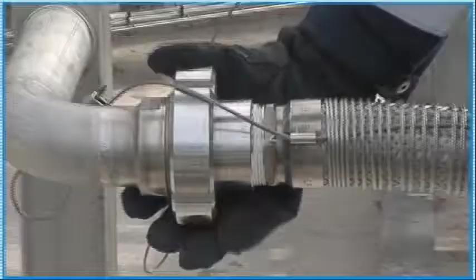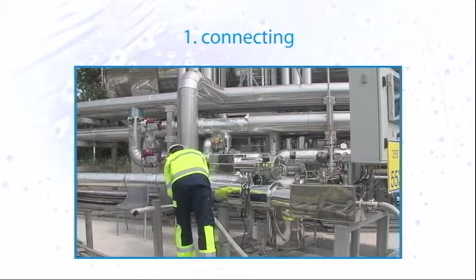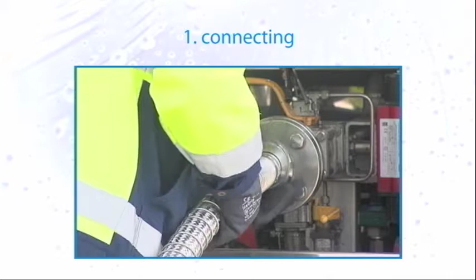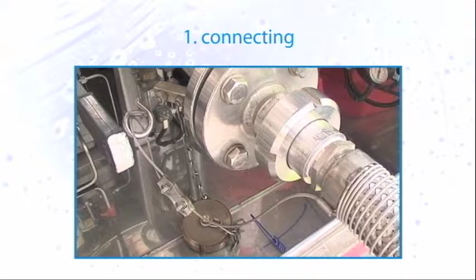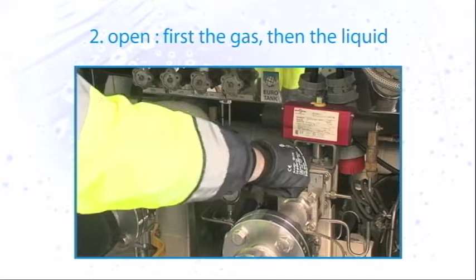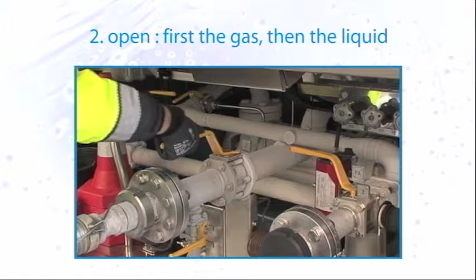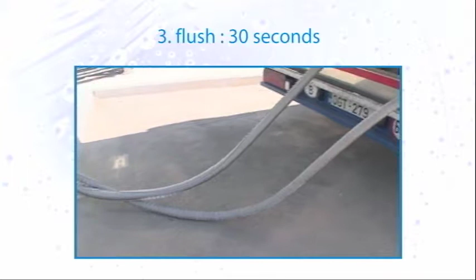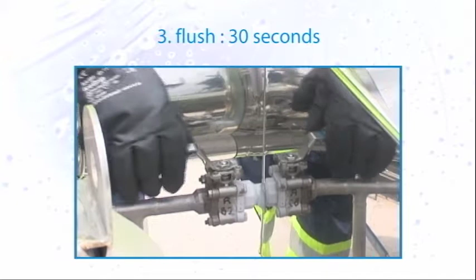Start with the correct connection of the liquid and gas hoses. For this, fasten the nuts good and tight. Now you can open the gas valve on the lorry. After that, the liquid valve. The connecting hoses are now flushed for about 30 seconds. Afterwards, you must close the valve to the collecting receptacle again.